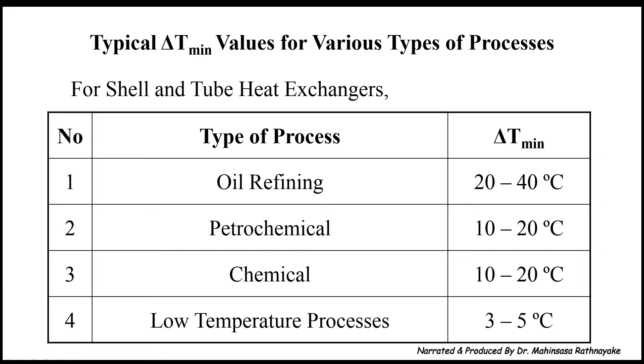For oil refining processes, the delta T minimum is generally taken between 20 to 40 degrees Celsius. For petrochemical applications, delta T minimum is taken from 10 to 20 degrees Celsius. Especially for chemical processes, the delta T minimum is generally taken between 10 to 20 degrees Celsius.